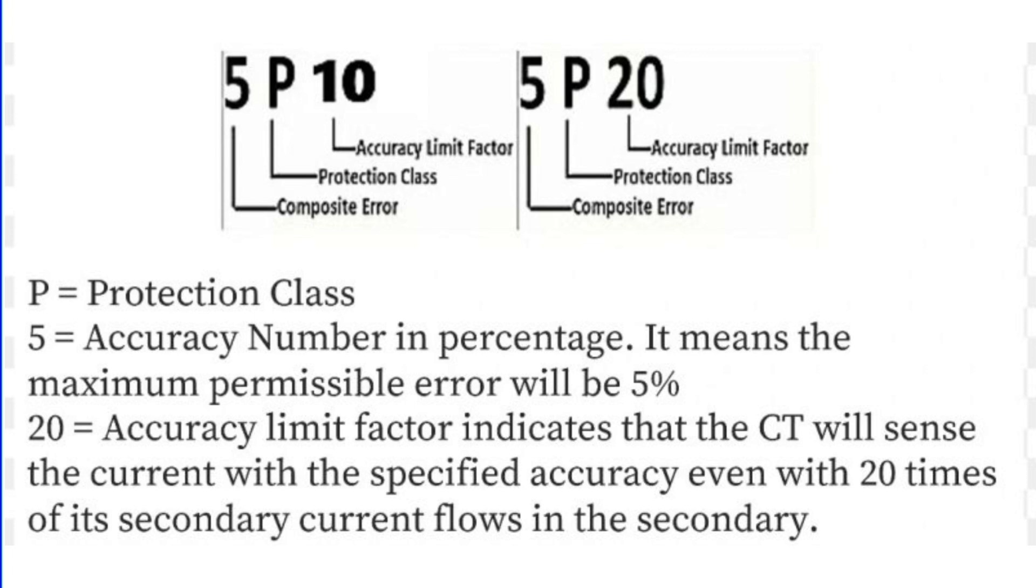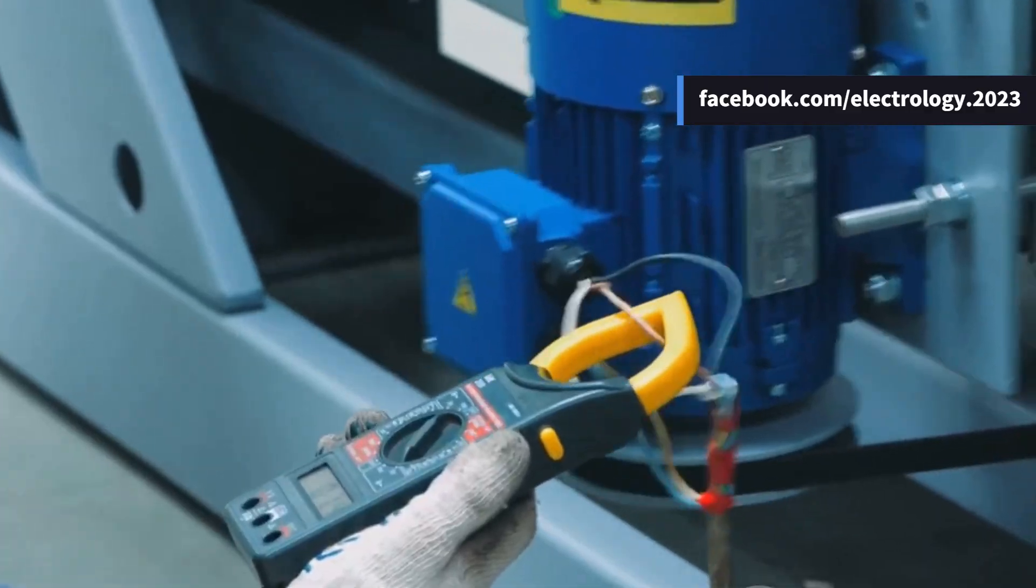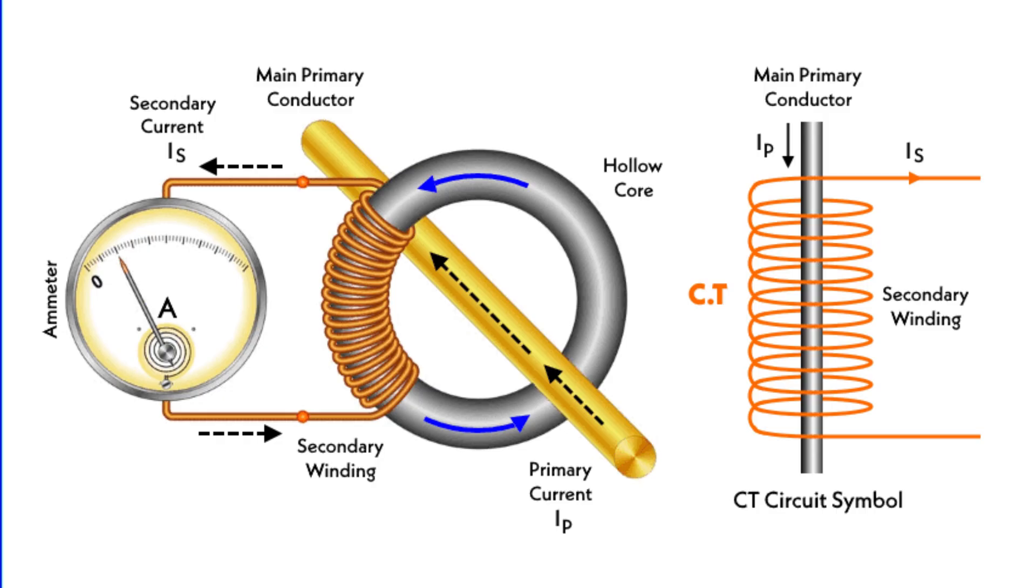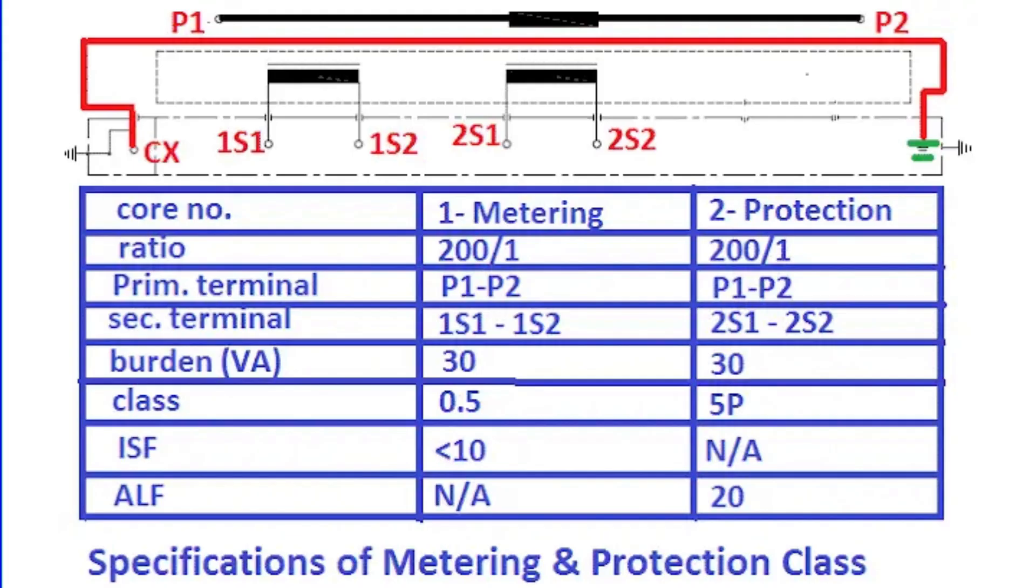Now let's talk about metering CTs. These CTs are optimized for measuring currents accurately when the primary current ranges from 1% to 120% of the rated current. A unique feature of metering CTs is the instrument safety factor or ISF, which protects meters during faults.